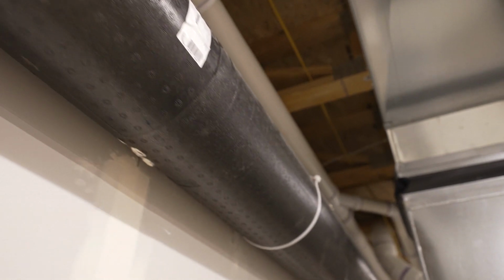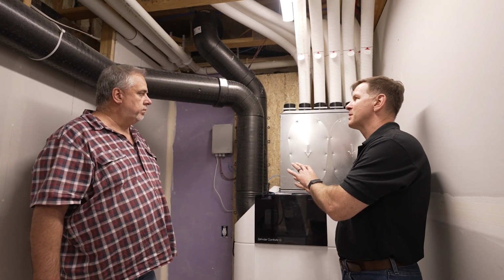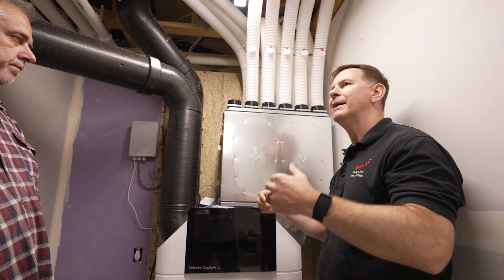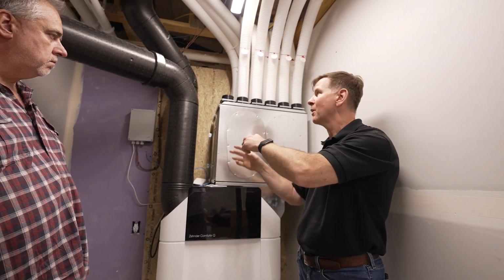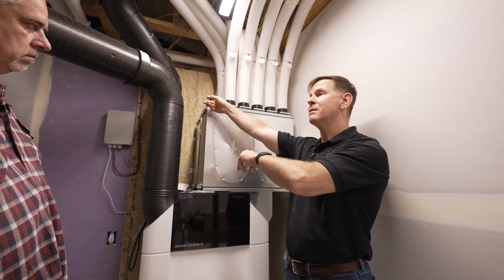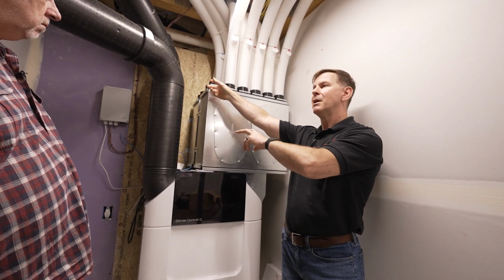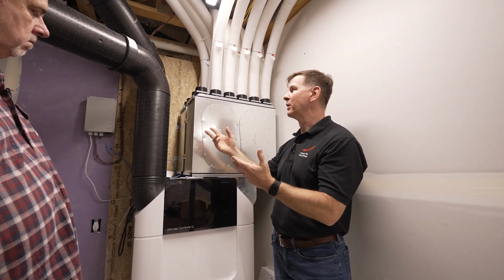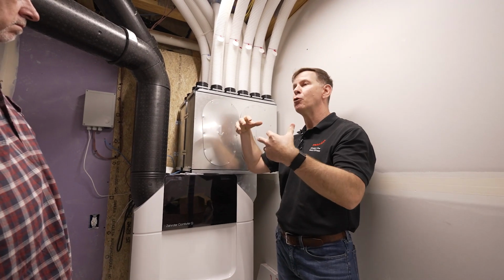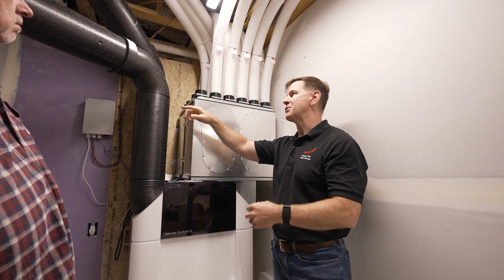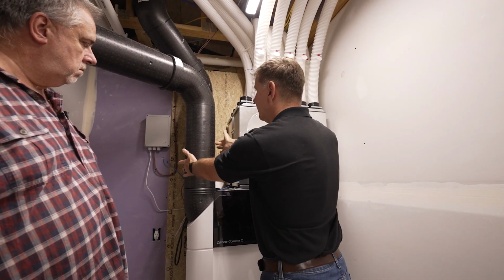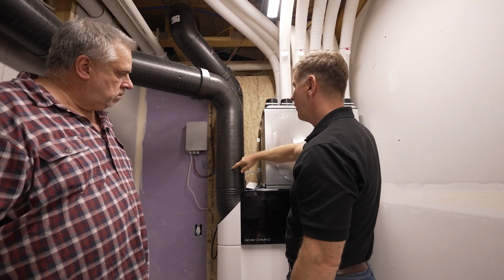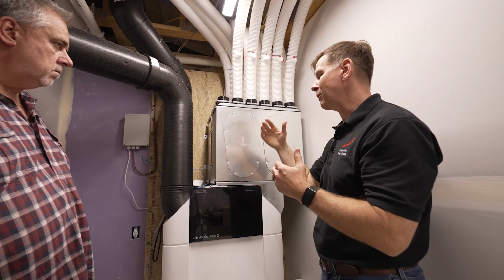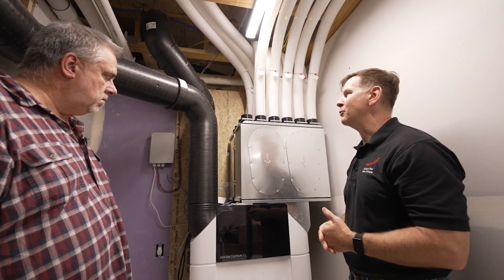Now, Chris, these are insulated. Talk to me about why. Yeah, so especially in the winter months, that's your biggest concern. If you don't have these ducts insulated, what's going to happen is you're going to get condensation around the outside. The interior air inside the ducts, both the exhaust duct and the intake duct, is cold air inside. So, if you've got cold air inside there and it drops below dew point in the room, then you're going to start getting sweating around the outside. So these are insulated, and they also have a vapor barrier. So in both cases, you're eliminating that dew point issue, and you won't have condensation.